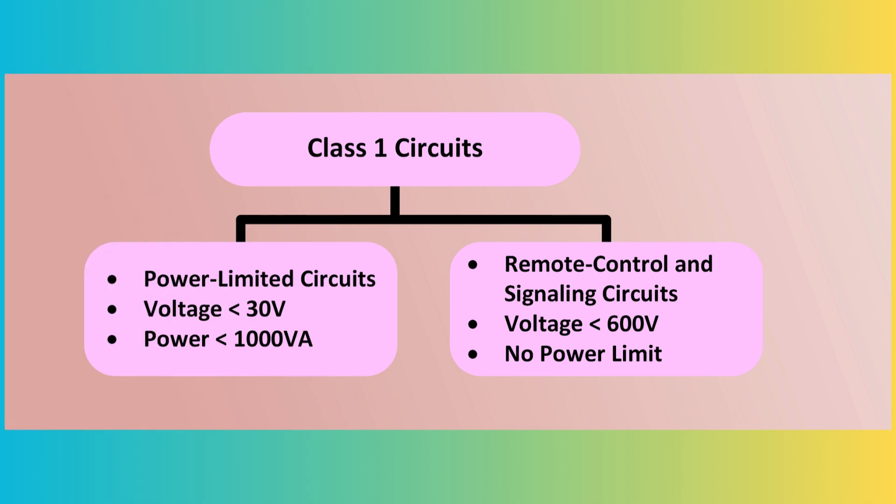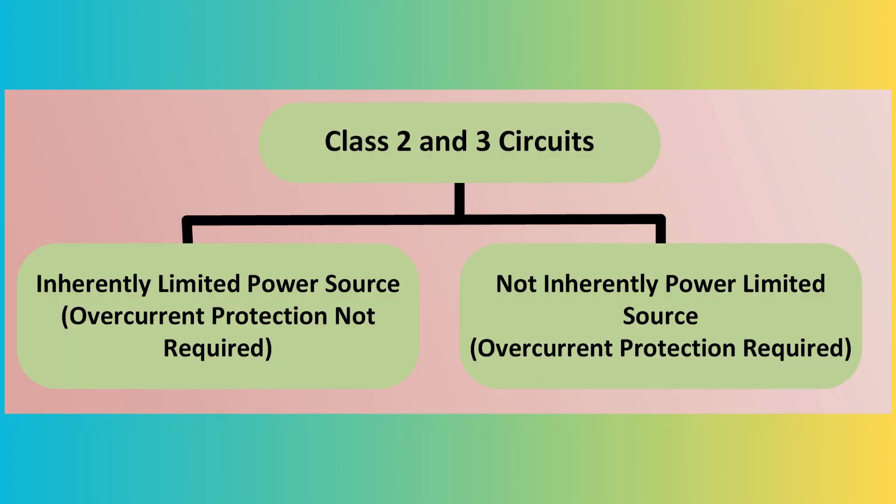Article 725 categorizes circuits into three classes based on power limitations: Class I, Class II, and Class III. Class I circuits are further divided into power-limited Class I circuits and remote-control and signaling Class I circuits. A common application of a Class I control circuit is the operating coil for a magnetic motor starter or lighting contactor. If the power levels specified for Class I circuits are exceeded, stricter material and installation requirements must be followed.